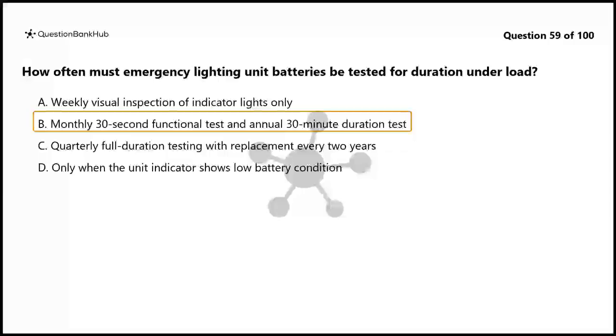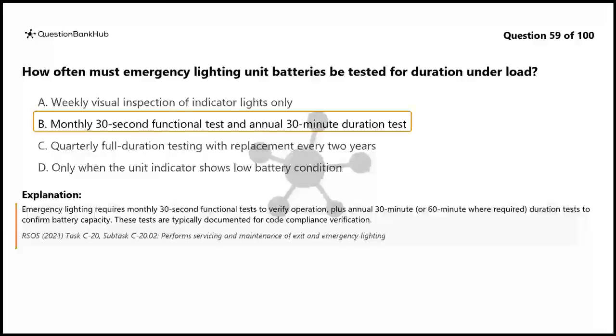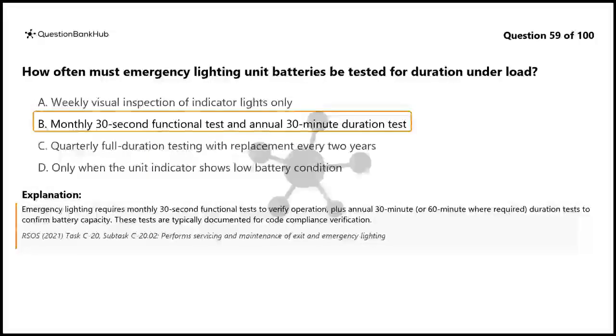The correct answer is B. Monthly 30-second functional test and annual 30-minute duration test. Emergency lighting requires monthly 30-second functional tests to verify operation, plus annual 30-minute, or 60-minute where required, duration tests to confirm battery capacity. These tests are typically documented for code compliance verification.